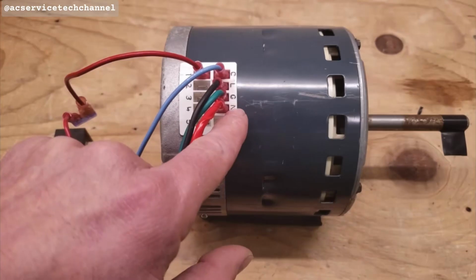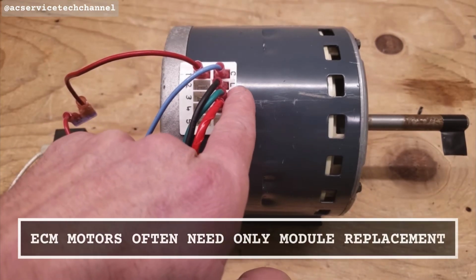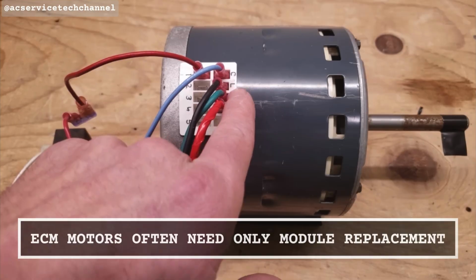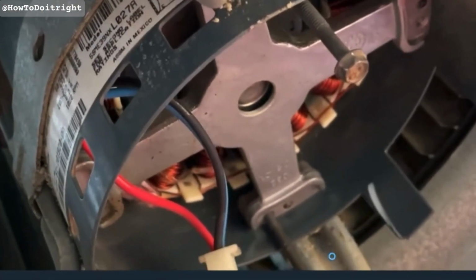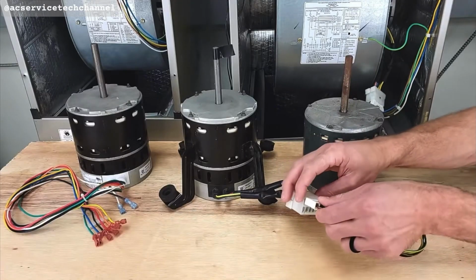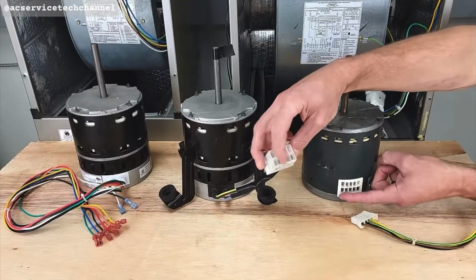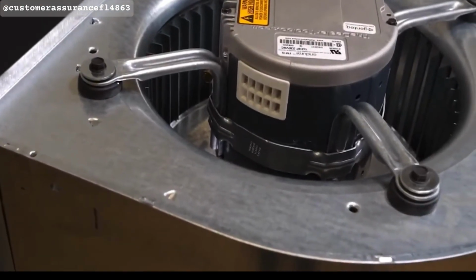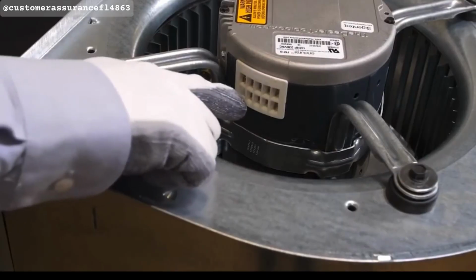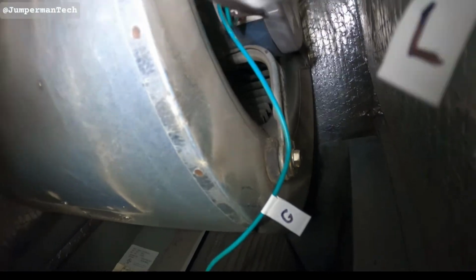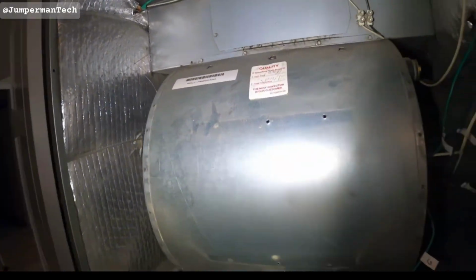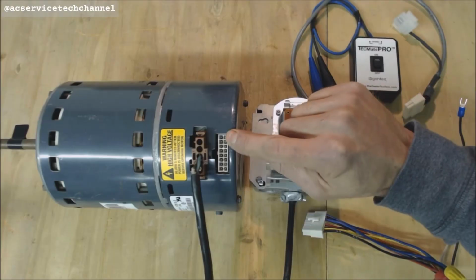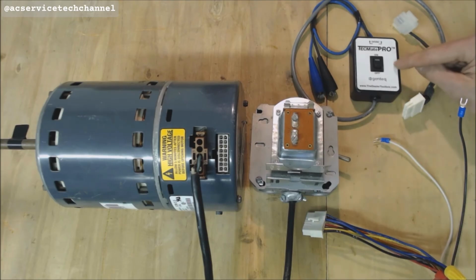Number 14. ECM blower motors and PSC blower motors fail differently and diagnose differently. PSC motors, the older single-speed type, fail with bad bearings or a bad run capacitor and you'll hear it coming. ECM motors, the electronically commutated type used on newer systems, fail at the integrated motor module, which is a control board built into the motor housing. ECM failures throw fault codes through the thermostat. Before you let a contractor replace the whole ECM motor at $800 to $1,200, ask if the module alone can be swapped for under $300. On most Carrier, Trane, and Lennox systems, it can.